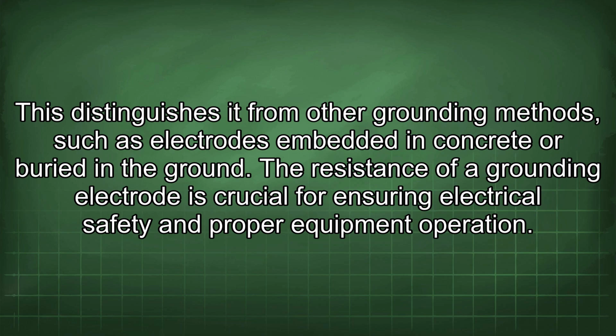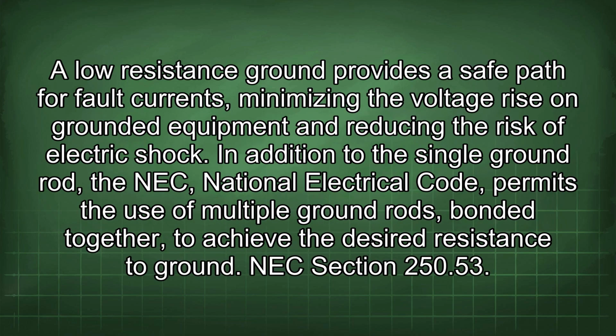The resistance of a grounding electrode is crucial for ensuring electrical safety and proper equipment operation. A low-resistance ground provides a safe path for fault currents, minimizing the voltage rise on grounded equipment and reducing the risk of electric shock. In addition to the single ground rod, the NEC, National Electrical Code, permits the use of multiple ground rods bonded together to achieve the desired resistance to ground.